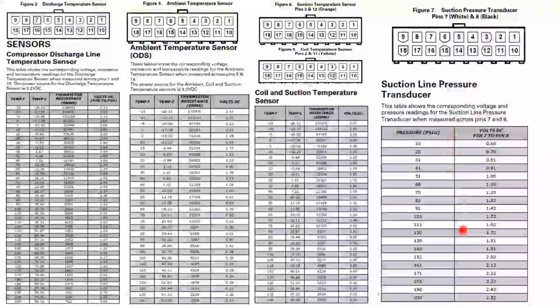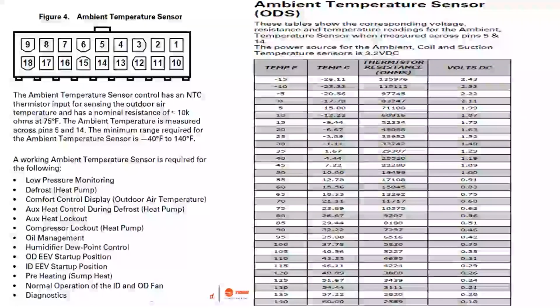So if you're showing 101 on your suction pressure, 1.52 volts DC across pins 7 and 8. So these two pins right here, if it's 101 suction pressure, better be 1.52 volts DC. So a lot of information in these charts. And each sensor comes into play. Like I said, there's only 5 of them.